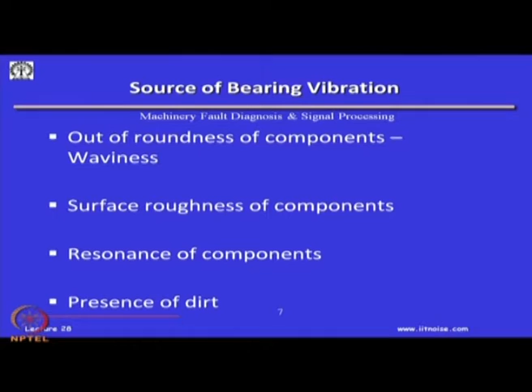Okay. And that is what people actually use in an instrument called a shock pulse meter. A shock pulse meter is actually nothing but a handheld instrument for bearing fault detection. It is nothing but a high frequency bearing vibration measurement, essentially a high frequency 20 to 30 kilohertz vibration measurement or monitoring device. High frequency vibration occurs in defective bearings because the resonant frequency of a defective race, because of a pit, scratch or dirt, gets excited, and you know the physics why it got excited: I excited the right hand side of the equation by a forcing function which happens to have the natural frequency of the system. Obviously, resonance happened and then I have high frequency vibrations.